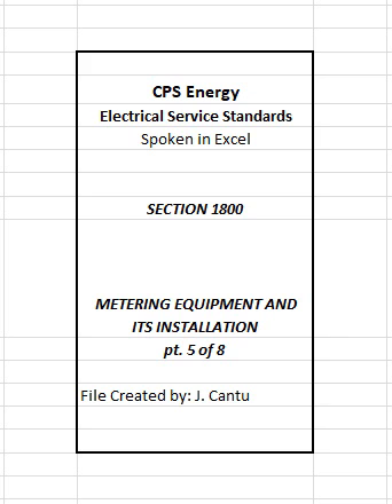Enclosures shall be corrosion-resistant, painted if steel, weatherproof where applicable, have removable covers which do not rely only on screws to secure them in position, be equipped with cover lifting handles as necessary for safety, and be constructed of minimum 12-gauge metal to prevent warping or bending. The enclosures must be sized in accordance with NEC and be equipped with padlock hasps or tongues and pentabolts. All custom-made enclosures shall first be approved by CPS Energy's Electric Service and Metering Standards Section.